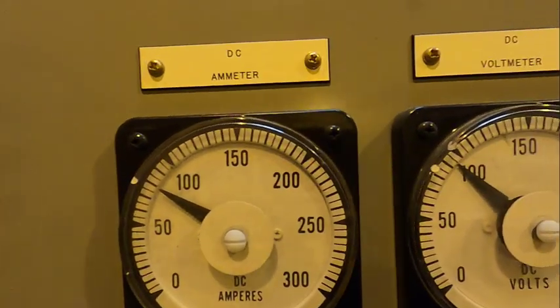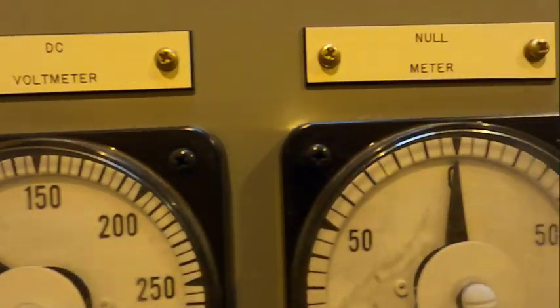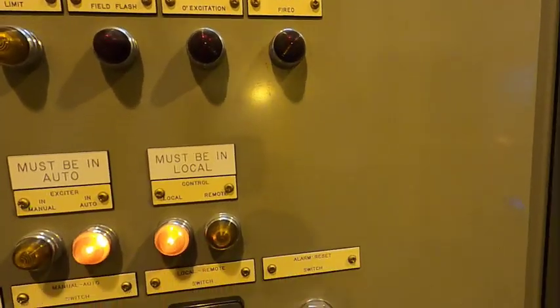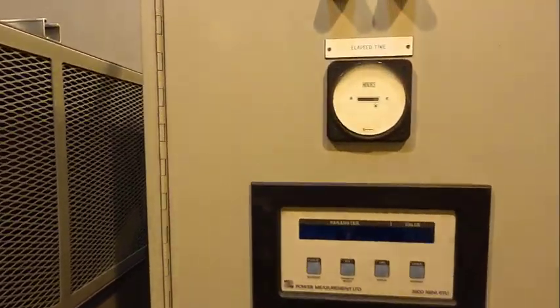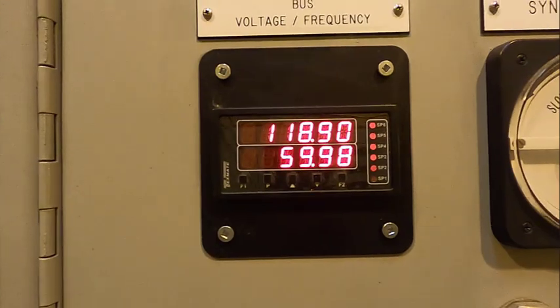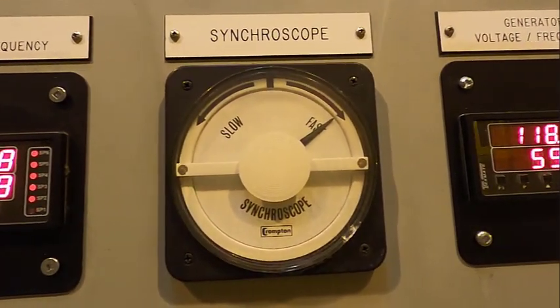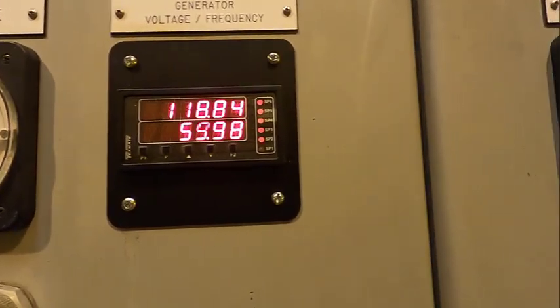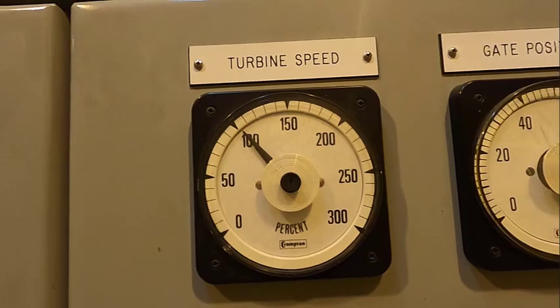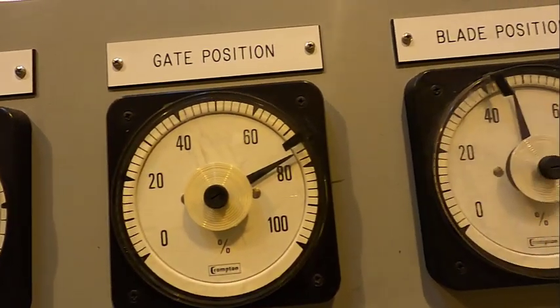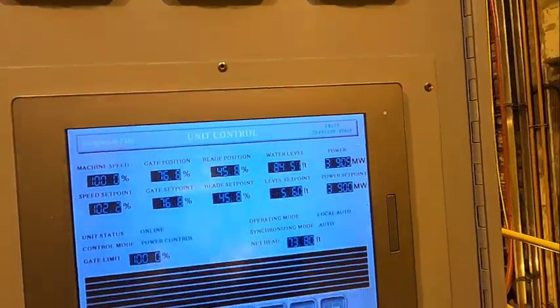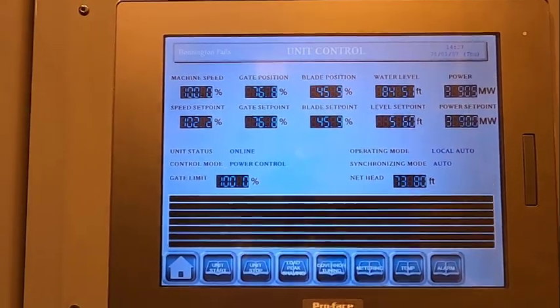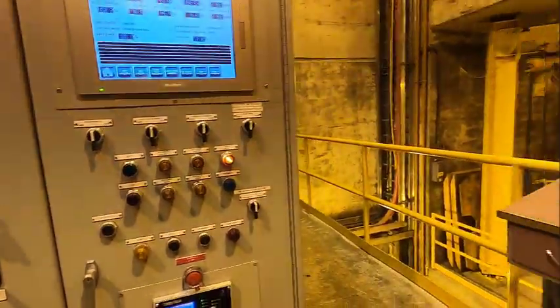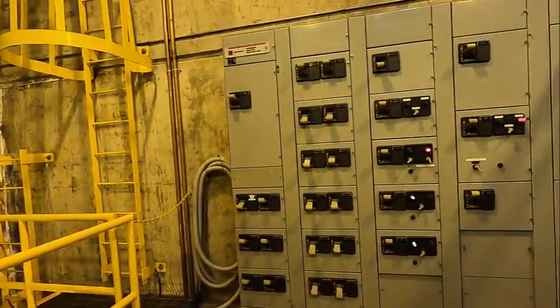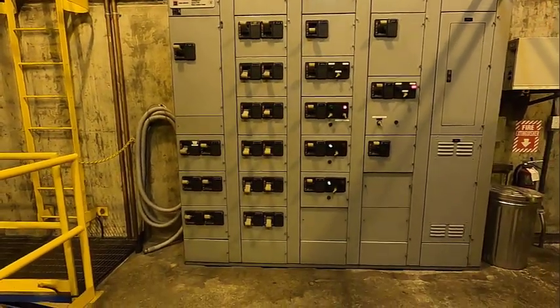We are now on the middle floor in Unit 5's building. This is our control center, showing us all of our various gauges for AC and DC amperage, voltage, as well as frequency. Here we can see that we are getting about 118.98 volts phase to phase at approximately 60 hertz. It shows us our speed of the turbine, the gate positions, and the blade positions. And then we have a digital control panel as well, and lots of other buttons. Here's our MCC unit to be able to lock out all of the pieces of equipment for Unit 5.